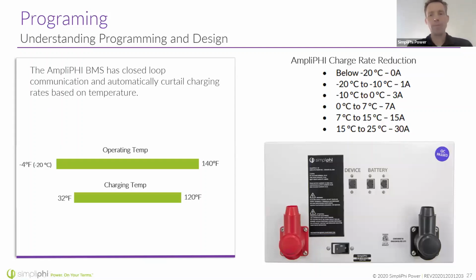So these batteries, the SimpliPhi battery and the SimpliPhi battery with the advanced communication system, even though it's recommended that you don't charge lithium batteries below 32 Fahrenheit, these batteries allow you to do that. They just reduce the rate of charge to prevent problems with intercalation. And so you can see that at very low temperatures, between -20 and -10 we slow down the charging to just 1 amp.